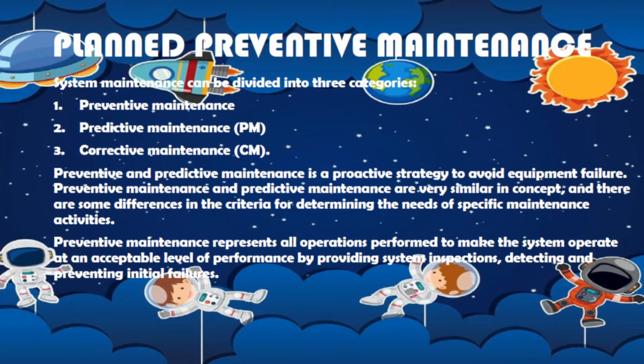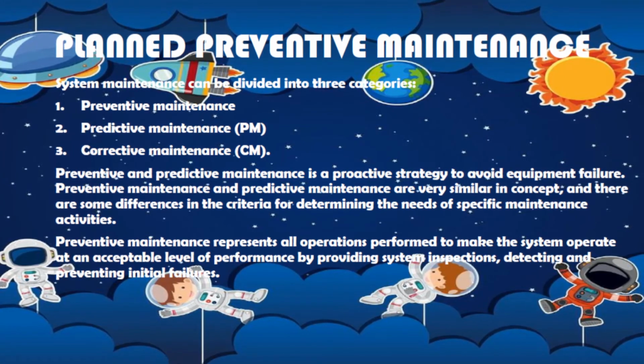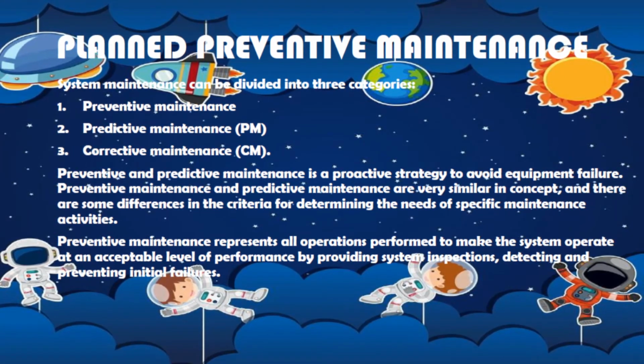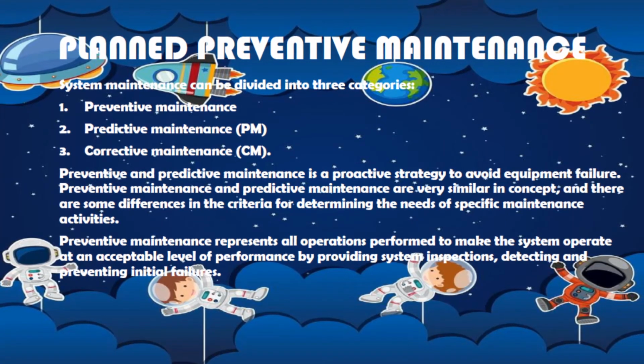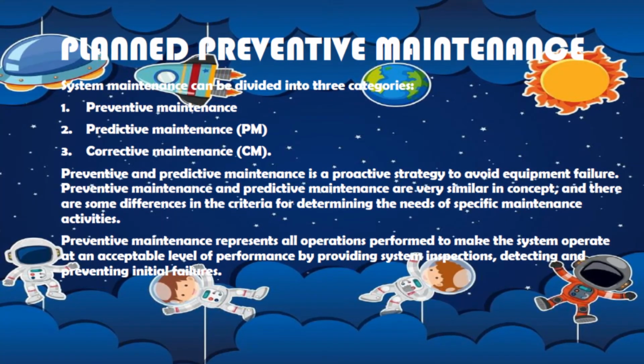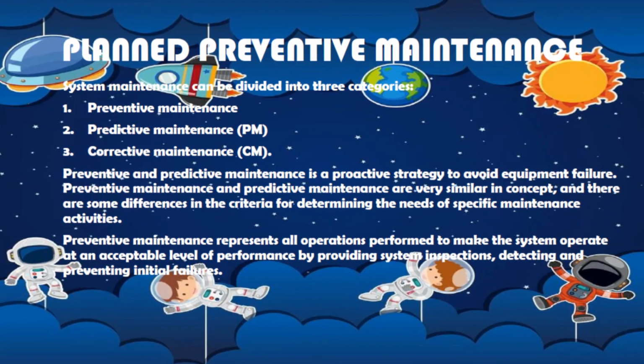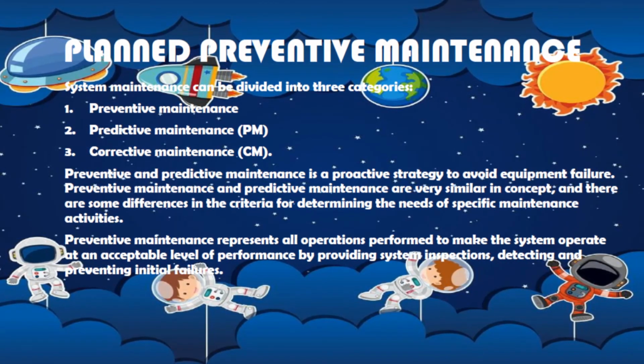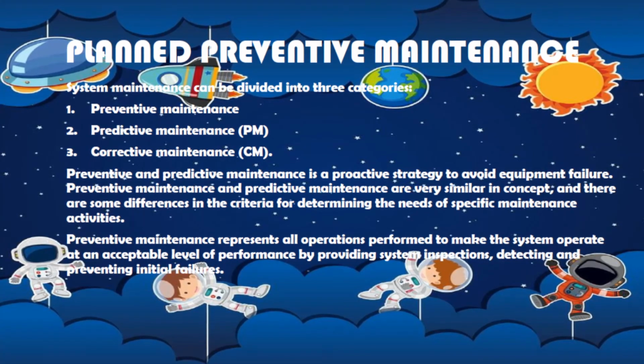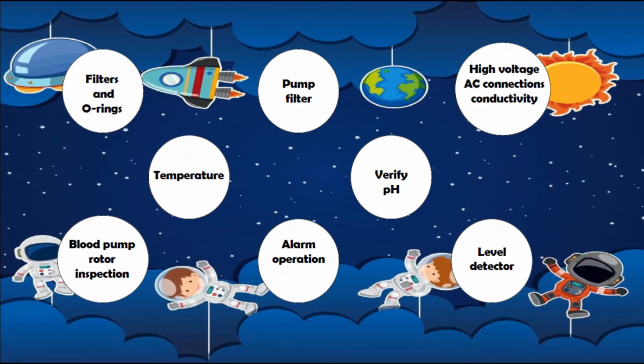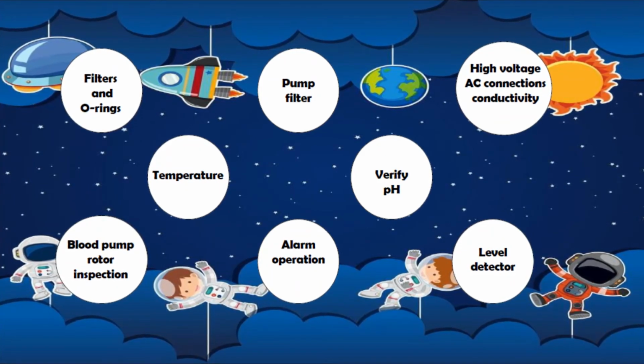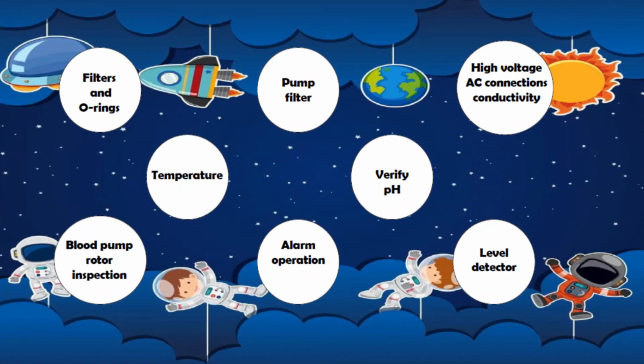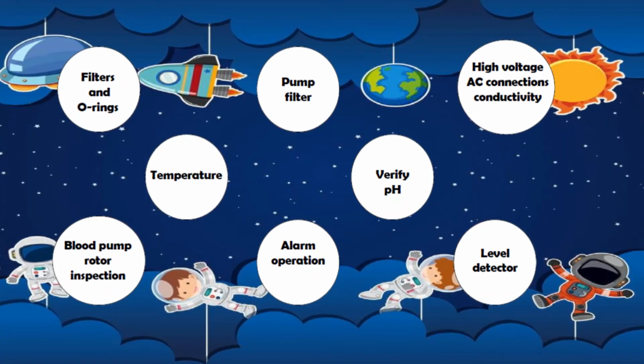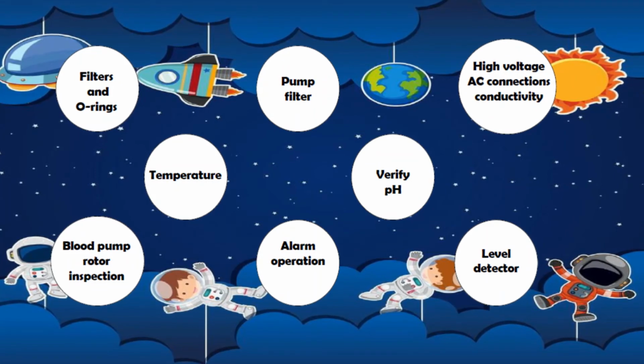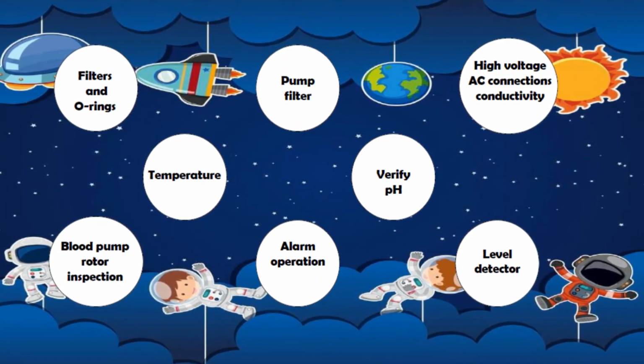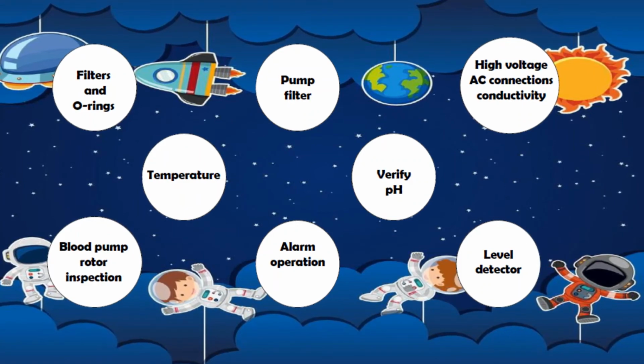equipment failure. Preventive maintenance and predictive maintenance are very similar in concept, and there are some differences in the criteria for determining the needs of a specific maintenance activity. Preventive maintenance represents all operations performed to make the system operate at an acceptable level of performance by providing system inspection, detecting and preventing initial failures. The type of maintenance that should be taken care of: filters and O-rings, blood pump rotor inspection, temperature, pump filter, alarm operation, verify pH, high voltage AC connections, conductivity, and level detector.